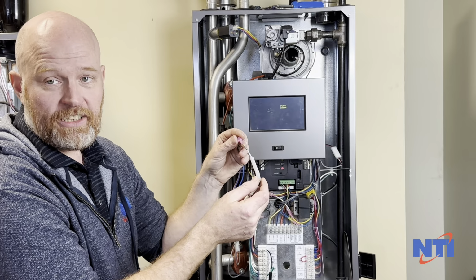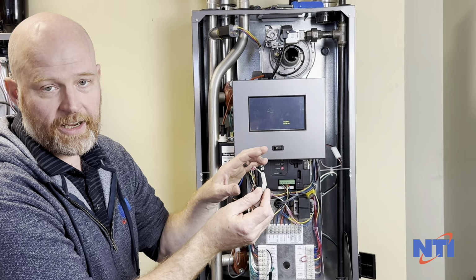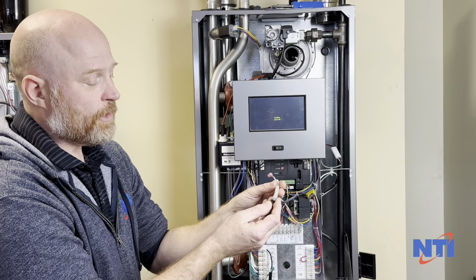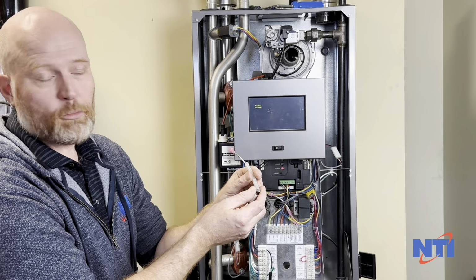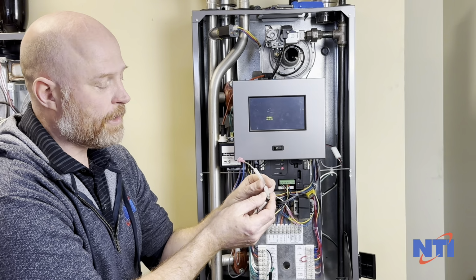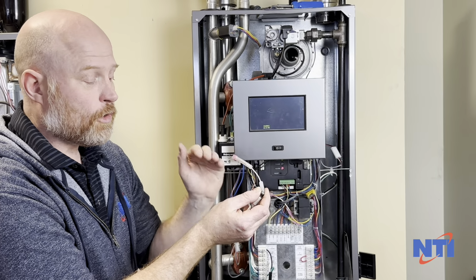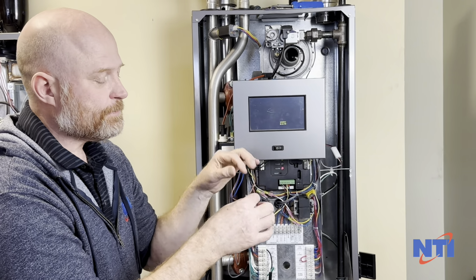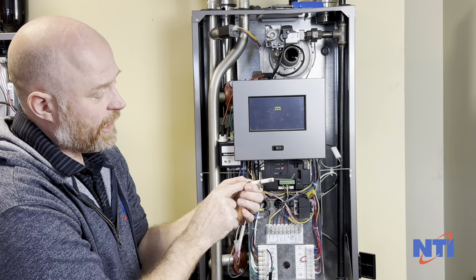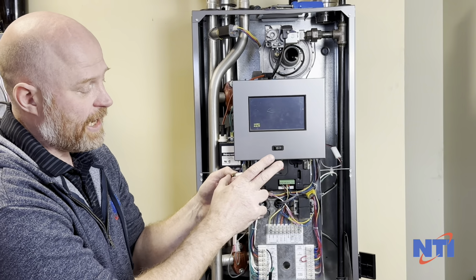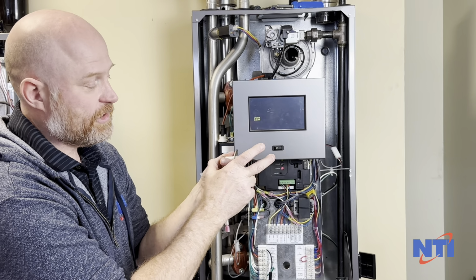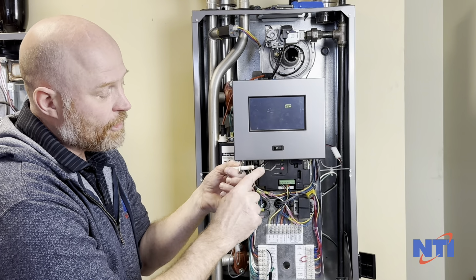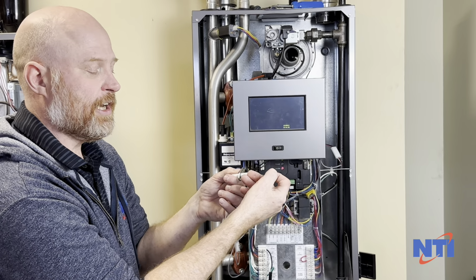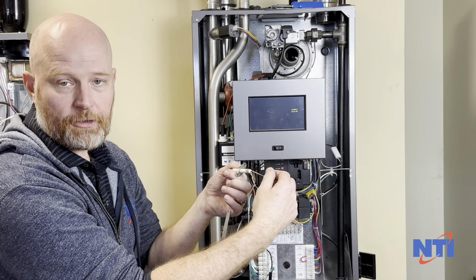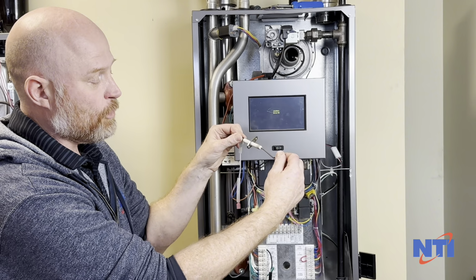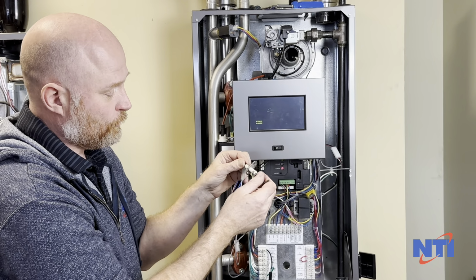Some of them may actually read 0 ohms because this is just a straight cable. If you're not sure, you can go to the NTI parts finder and look up the cable for your boiler and see if it has resistors or not. The electrical diagram for the boiler also indicates which ones have resistors. You can test your flame rod from tip to tip. This should have effectively 0 to 1 ohms of resistance or very little resistance. You do get some corrosion on here, so it's important that you give it a little scratch or something just to make sure your meter makes a good contact on both sides. And again, you should have continuity through the rod.